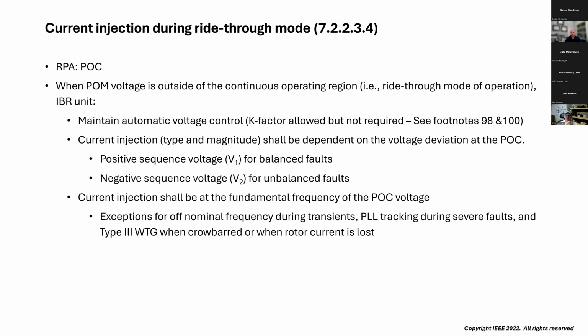Okay, so that's how you're going to set the control modes up on the front end. But then the question is, what do we do with that? The first thing is, once the POM voltage goes outside of the continuous operating range, so you're in a ride through mode of operation, you need to maintain automatic voltage control. There are a couple footnotes related to K factor. One basically says that yes, K factor is automatic voltage control. It's closed loop control via proportional gain. And the other one says that K factor is not required. So you can use any control approach you want as long as you can meet the control objectives.